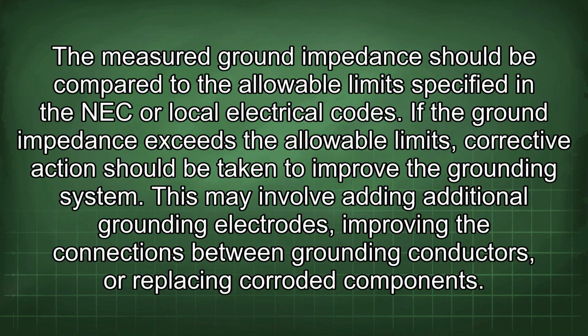The measured ground impedance should be compared to the allowable limits specified in the NEC or local electrical codes. If the ground impedance exceeds the allowable limits, corrective action should be taken to improve the grounding system. This may involve adding additional grounding electrodes, improving the connections between grounding conductors, or replacing corroded components.